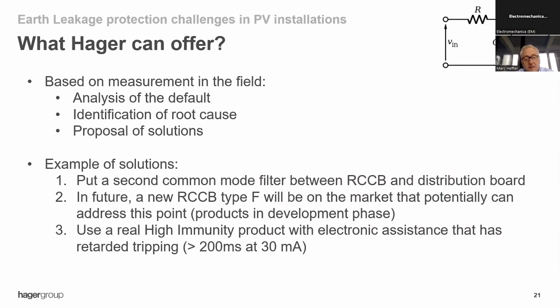Another possibility, and this depends on what I explained about the curves and the levels of leakage current, would be to use the type F that will arrive on the market in the future, but you can still use high immunity products. High immunity means with electronic assistance. The RCCB has electronic assistance because these products trip with a delay. So instead of tripping within 40 milliseconds, they trip after more than 200 milliseconds. And this could be enough, again, depending on this transition current. This could be enough in some cases to solve the problem.